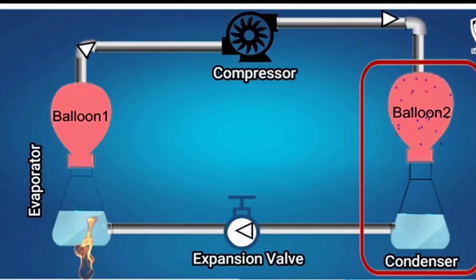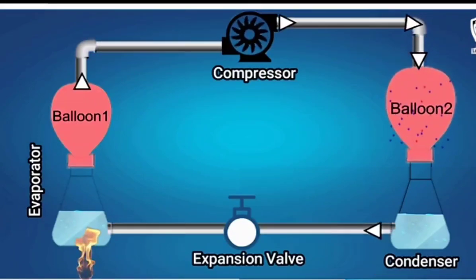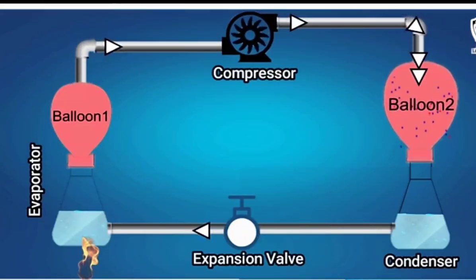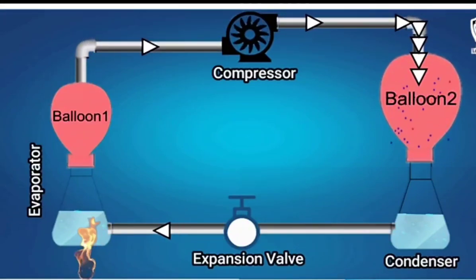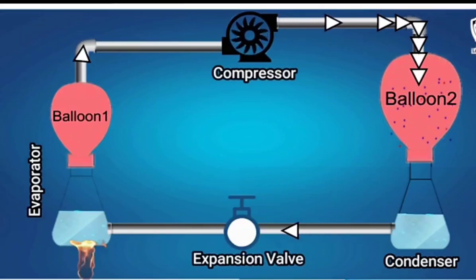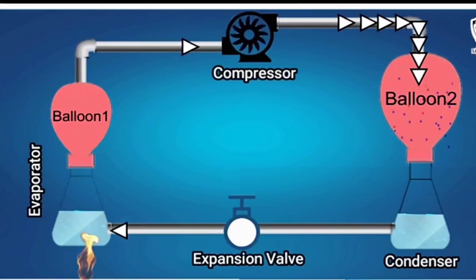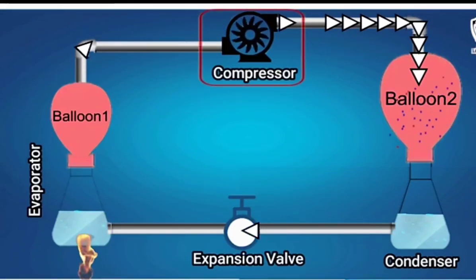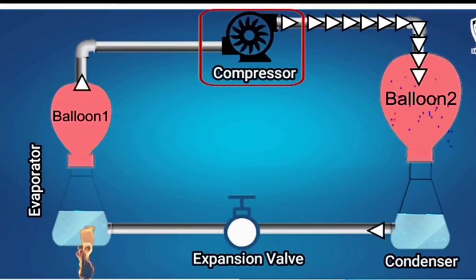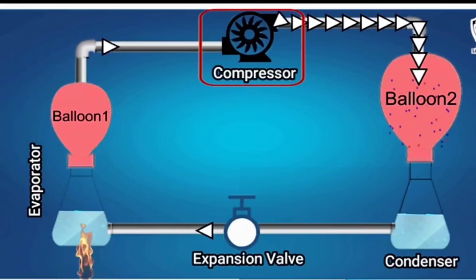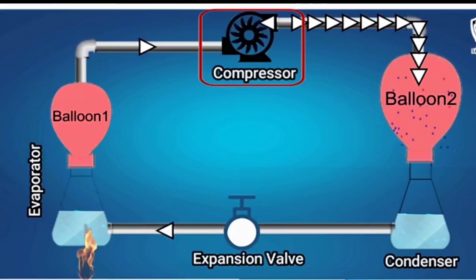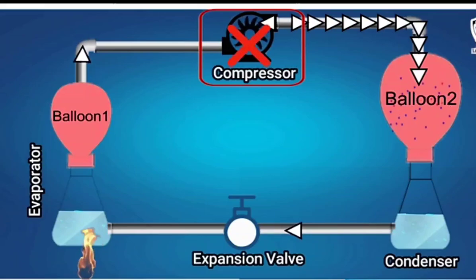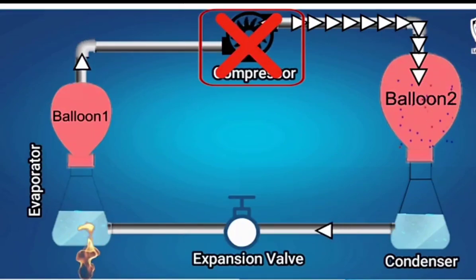At some point, the pressure inside the balloon becomes so high that it reaches a point where no more vapor can enter. At this point, the compressor will continue to try to push vapor in. But the vapor, unable to enter the balloon, will stop and try to enter the compressor again. Thus, when vapor returns, it affects the compressor more. This is what we call chiller surge.